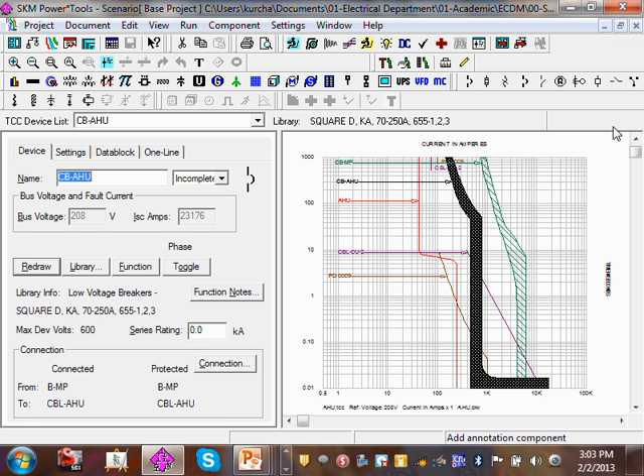and then it goes back to stable and runs forever at this value. So if you guys look at the green and the black, are they touching each other? The only place they're touching each other is right here, slightly, so they're fully coordinating. So if I have a short circuit anywhere from this point all the way down in the air handling unit, I'm guaranteed that the only circuit breaker that's going to trip is the circuit breaker ahead of the air handling unit, not the main. So everybody's happy, right? You don't want to trip the main every time.